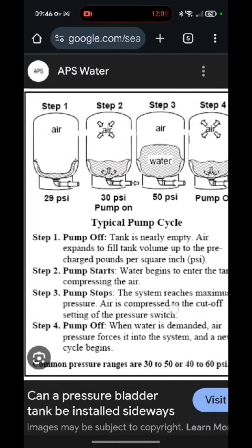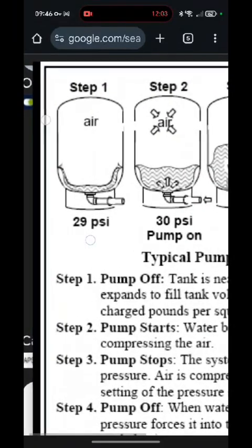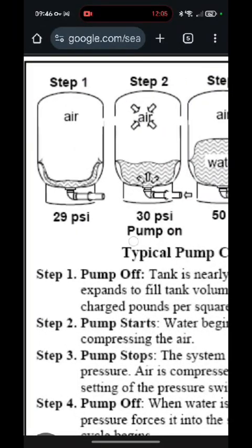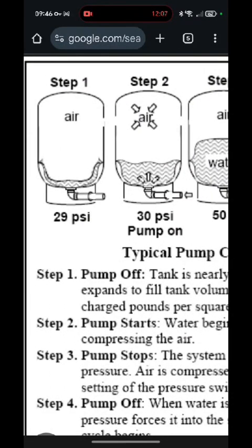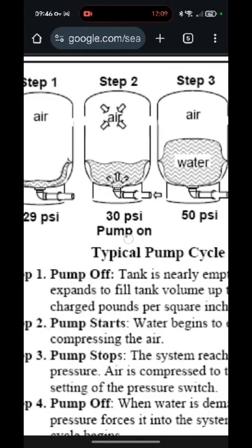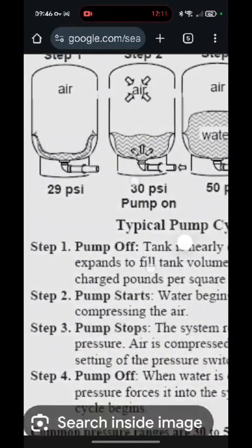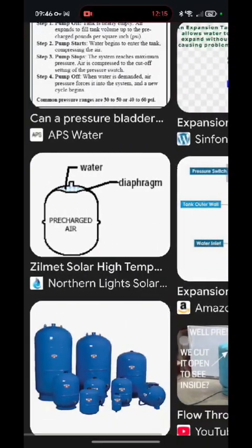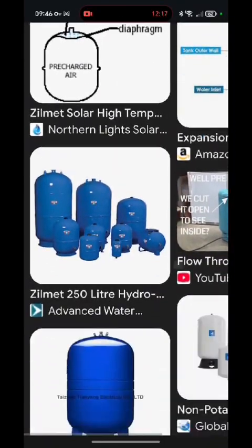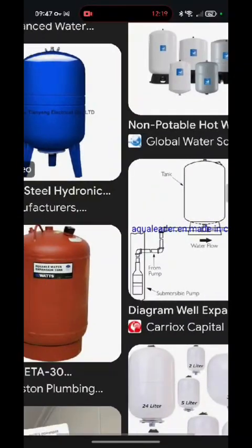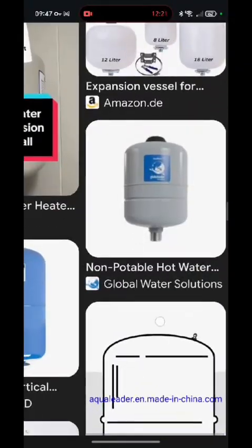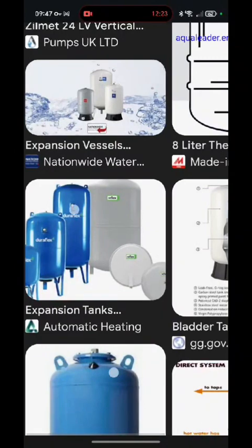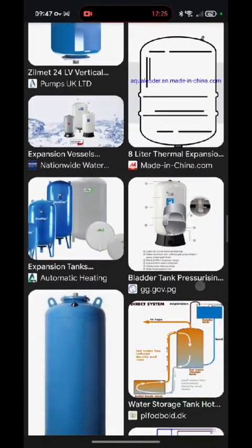And there we go, you see? This is a great example. Air is in there, the bladder is held in place, and then as it expands, it can slightly break the seal. So just by reseating it, that can repair it sometimes. And again, if we're trying to save the customer money, sometimes when they don't have it straight away, if you can at least save the vessel, you just buy them a bit more time.